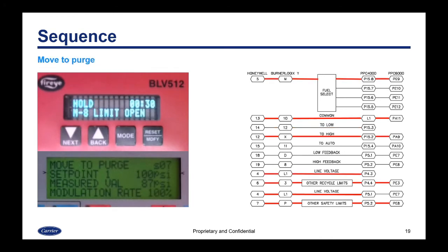Next we're going to move to purge. So the sequence has been started. Power comes through the blower output, goes through the fuel select switch, and chooses a profile selection. At which point the flame safeguard now wants the PPC to drive to high, so it sends a command to that. Now the recycle limits are also closed, safety limits are closed. So this is the display you're going to see. Move to purge, and the flame safeguard is going to say that it's waiting for the limit to be proven.